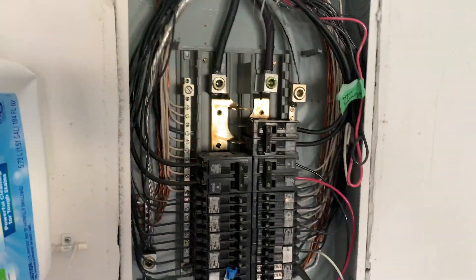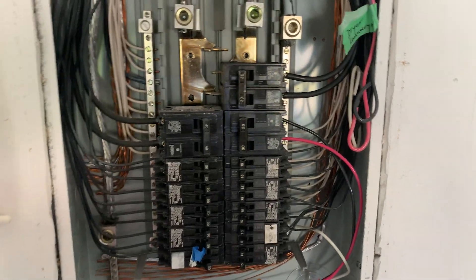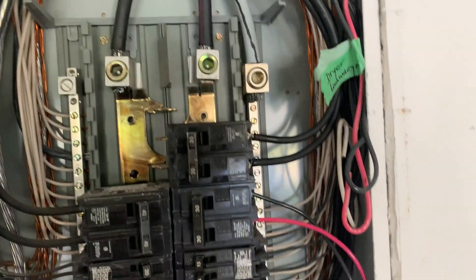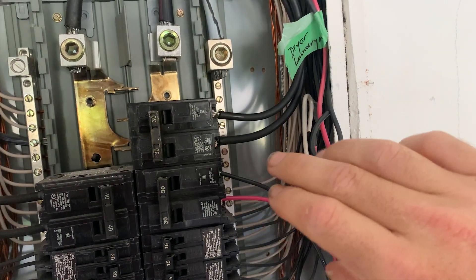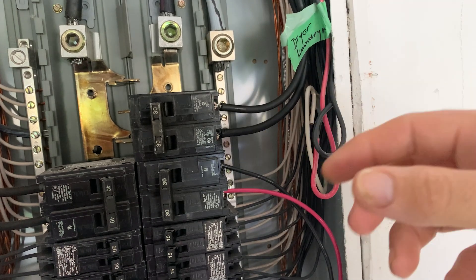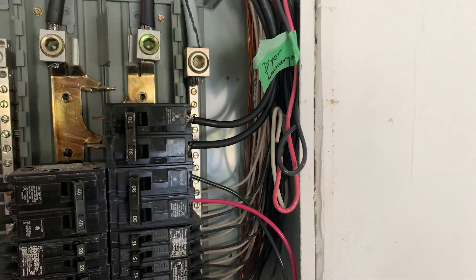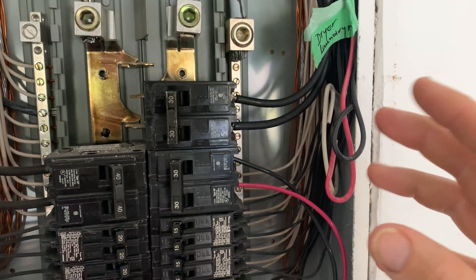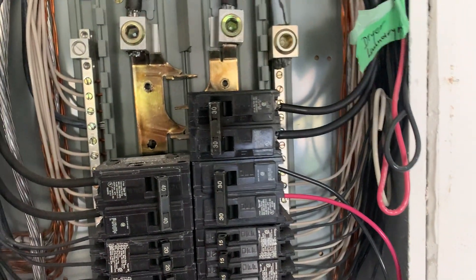Bert finds a real life problem with a circuit breaker. Guys, we've got a breaker tripping periodically for our condenser. The first thing I think about when a breaker is tripping periodically is that we have a poor connection point somewhere. That could be a loose wire going into anywhere on the high voltage circuit, or a corrosion issue where a connection point has broken down and is starting to arc. One of the telltale signs is your breaker picks up heat as it starts running — you're pulling normal amp draws from your system, but your wires and breaker are getting hot.